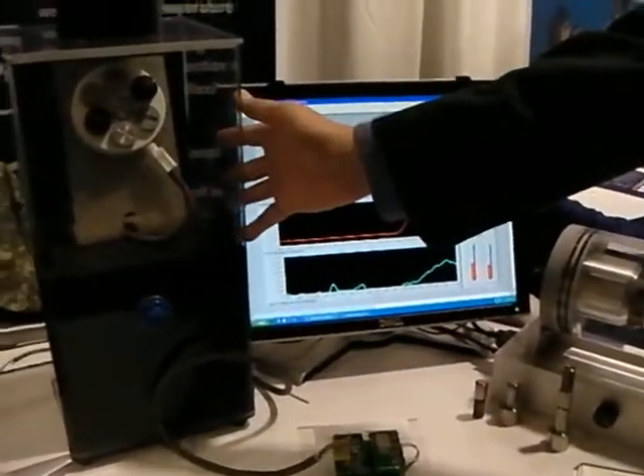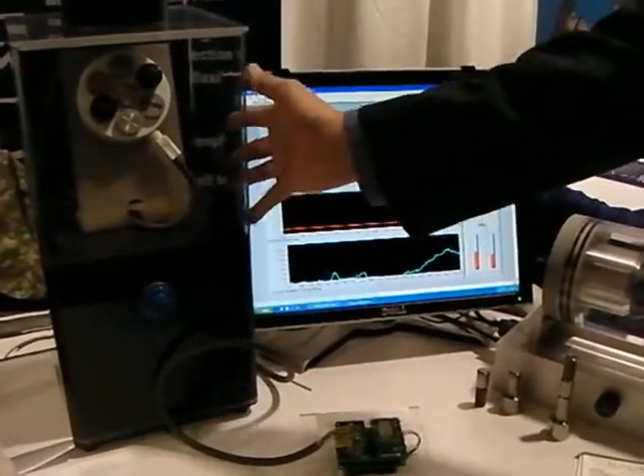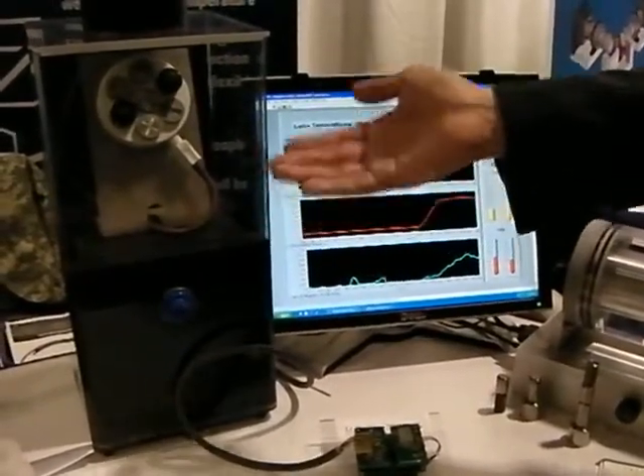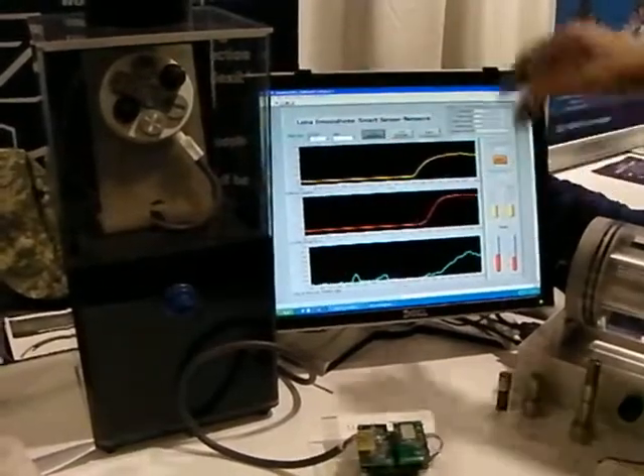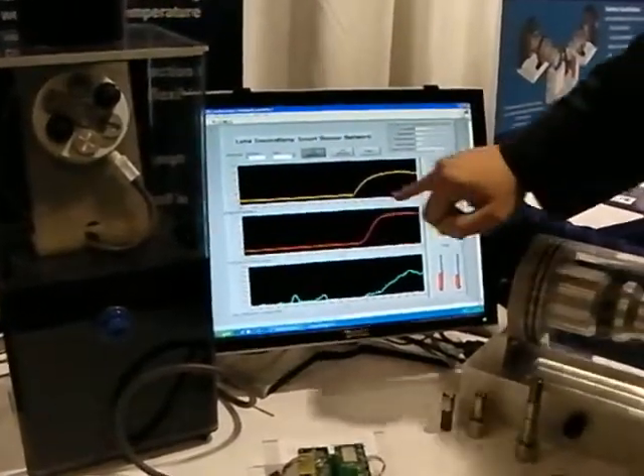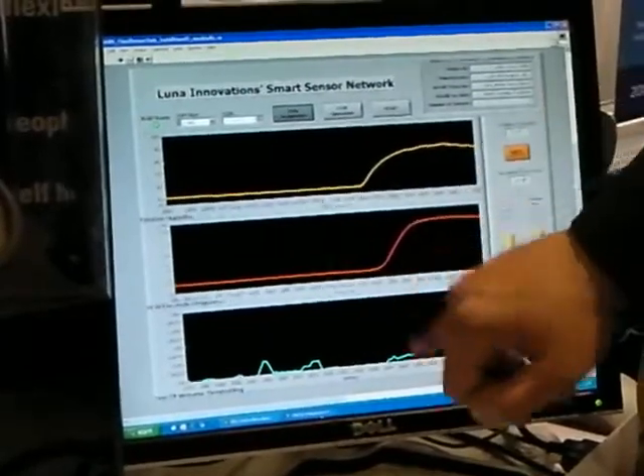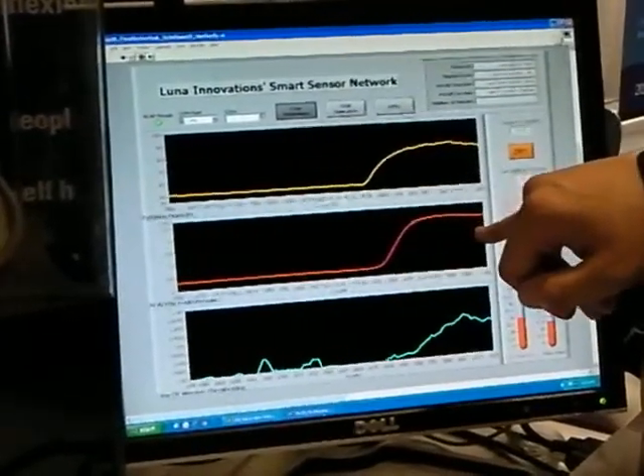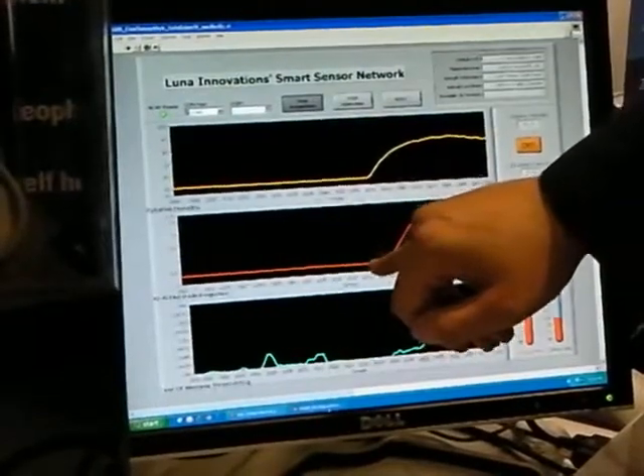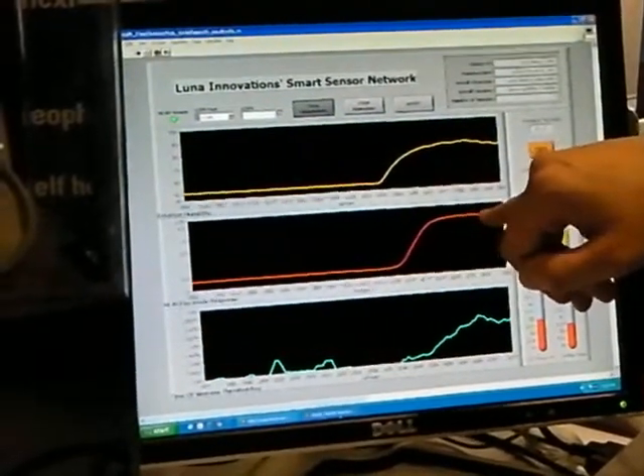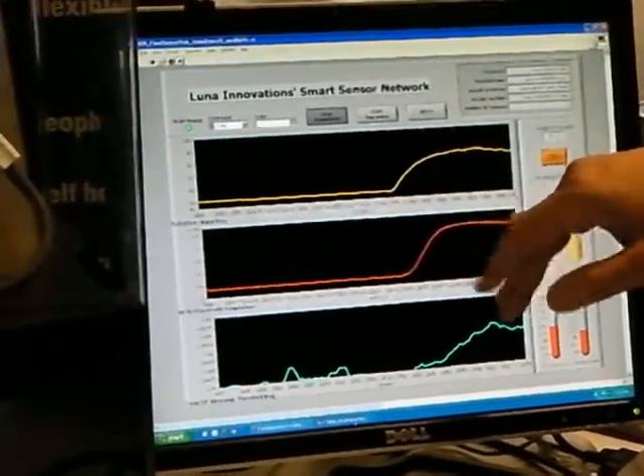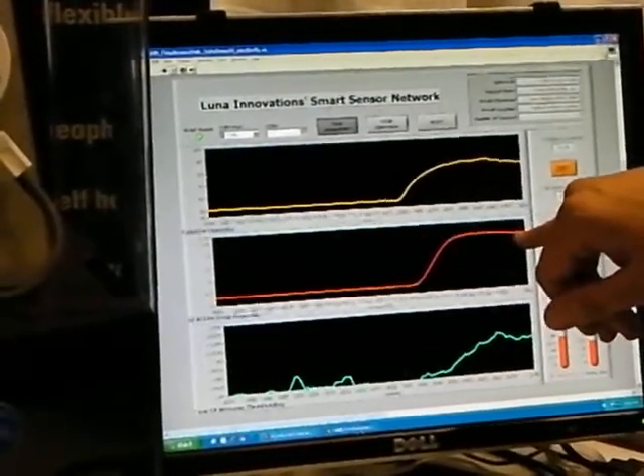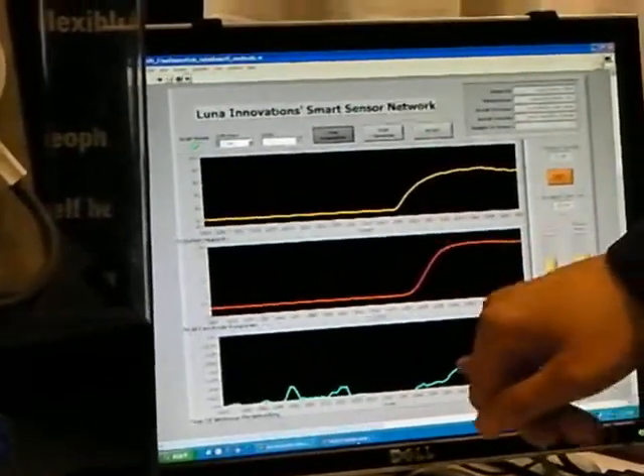In this chamber we have a humidifier which allows us to increase and decrease the humidity that these sensors are exposed to. What you can see on the screen here is as we increase the humidity, we get significant responses in our aluminum electrode response, which shows us that as we increase humidity we get a layer of water on that sensor and it begins to corrode. And we can actually measure the rate of corrosion on that sensor.